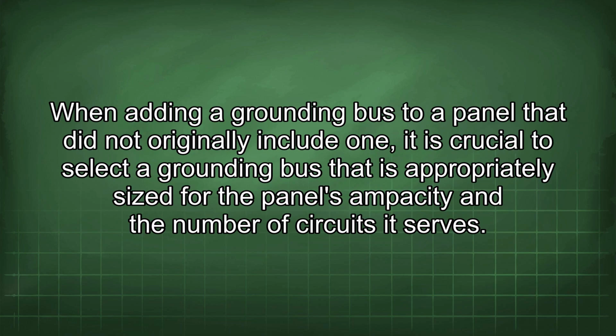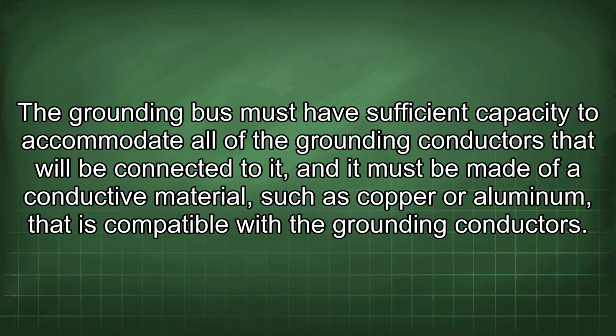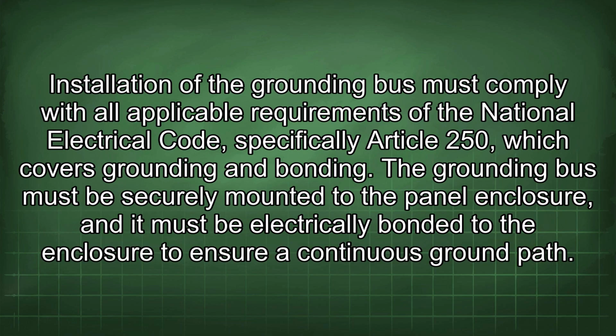When adding a grounding bus to a panel that did not originally include one, it is crucial to select a grounding bus that is appropriately sized for the panel's ampacity and the number of circuits it serves. The grounding bus must have sufficient capacity to accommodate all of the grounding conductors that will be connected to it, and it must be made of a conductive material, such as copper or aluminum, that is compatible with the grounding conductors. Installation of the grounding bus must comply with all applicable requirements of the National Electrical Code, specifically Article 250, which covers grounding and bonding. The grounding bus must be securely mounted to the panel enclosure, and it must be electrically bonded to the enclosure to ensure a continuous ground path.